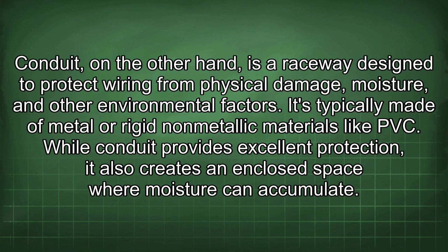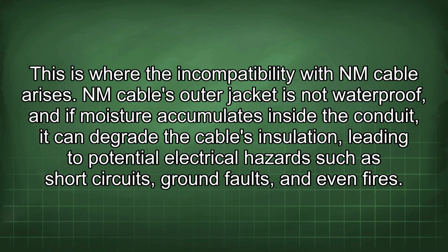Conduit, on the other hand, is a raceway designed to protect wiring from physical damage, moisture, and other environmental factors. It's typically made of metal or rigid non-metallic materials like PVC. While conduit provides excellent protection, it also creates an enclosed space where moisture can accumulate. This is where the incompatibility with NM cable arises. NM cable's outer jacket is not waterproof, and if moisture accumulates inside the conduit, it can degrade the cable's insulation, leading to potential electrical hazards such as short circuits, ground faults, and even fires.